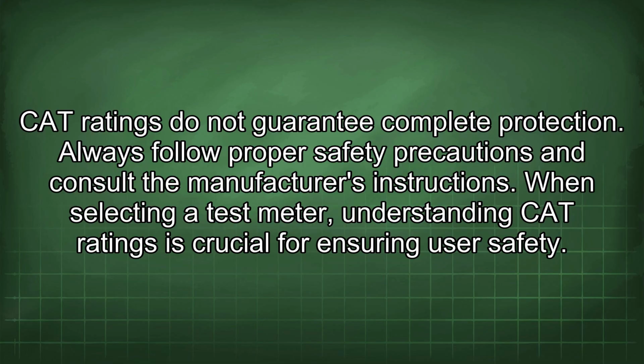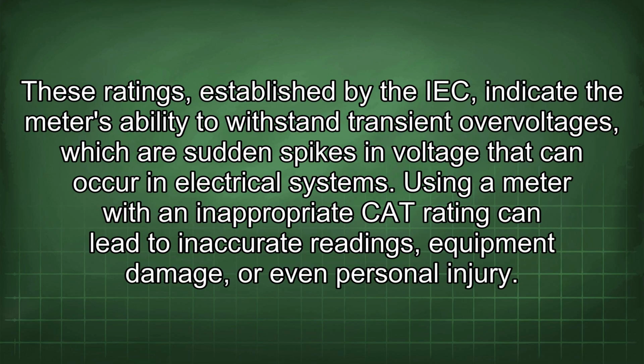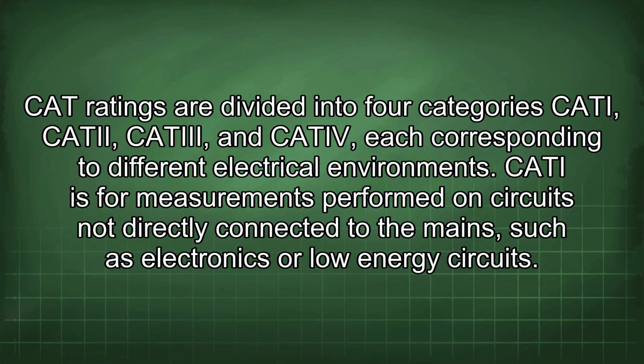When selecting a test meter, understanding CAT ratings is crucial for ensuring user safety. These ratings, established by the IEC, indicate the meter's ability to withstand transient overvoltages, which are sudden spikes in voltage that can occur in electrical systems. Using a meter with an inappropriate CAT rating can lead to inaccurate readings, equipment damage, or even personal injury. CAT ratings are divided into 4 categories: CAT I, CAT II, CAT III, and CAT IV, each corresponding to different electrical environments.